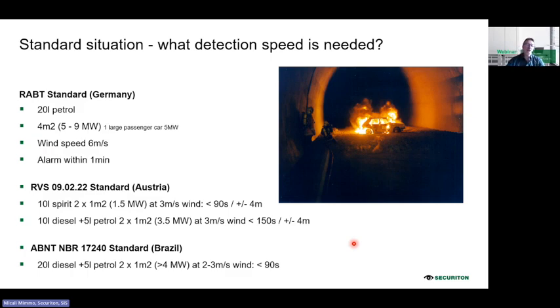So let's have a look maybe at 3 standards here. We have the German standard. They use quite a lot of petrol, 20 liters on 4 square meters. This will generate power of approximately 5 to 9 megawatts. 5 megawatts is when a passenger car is burning, like we see here in the picture. Then 9 megawatts could be also a little van or a little bus. So this is to give an idea what kind of power these fires generate.